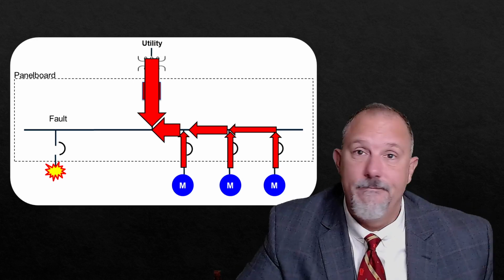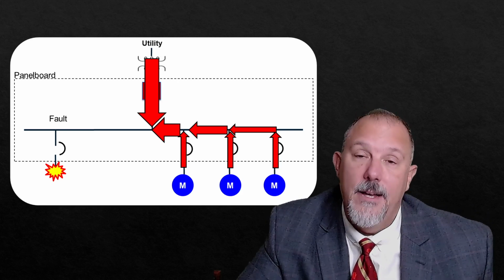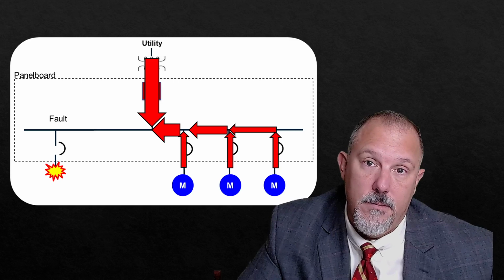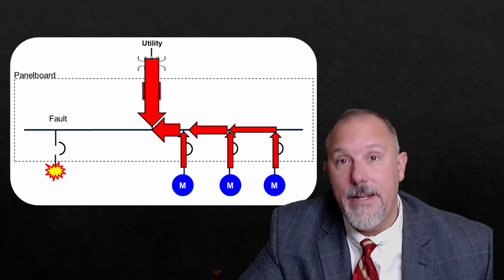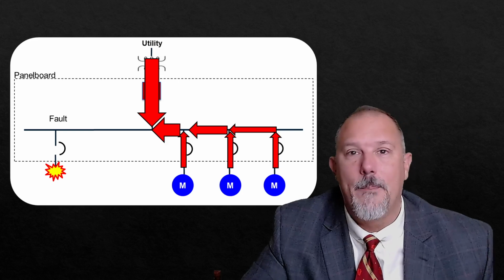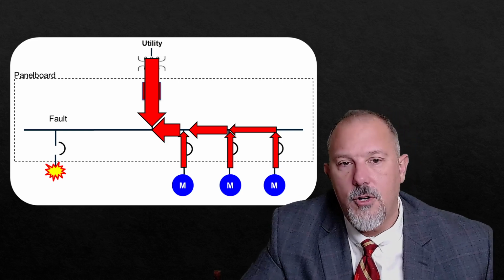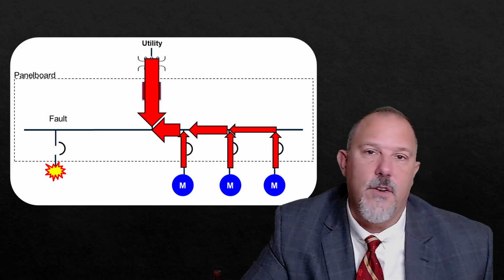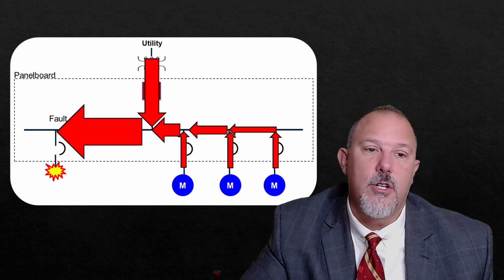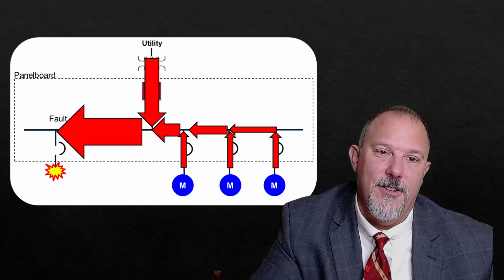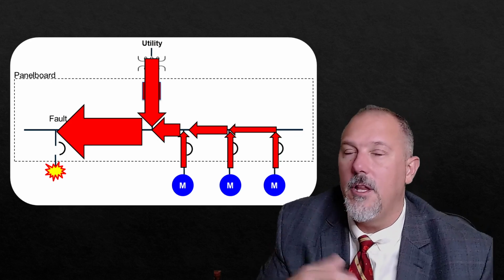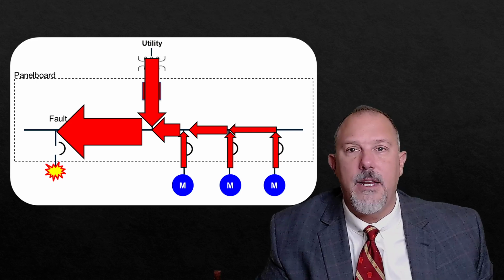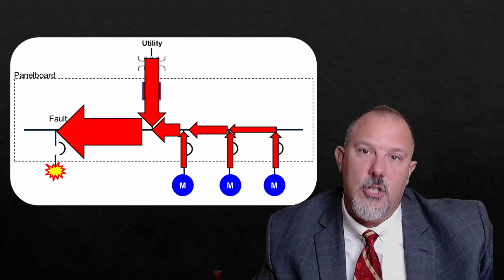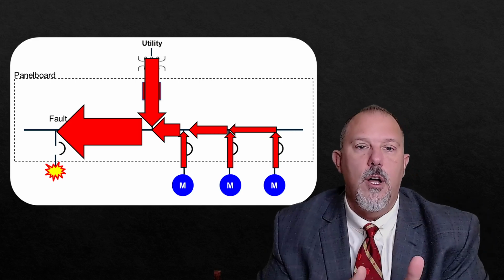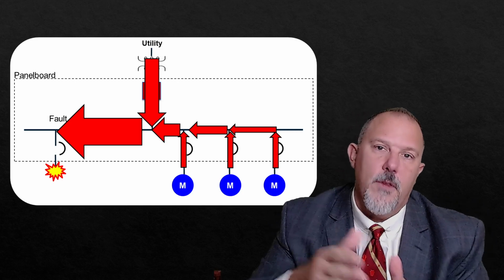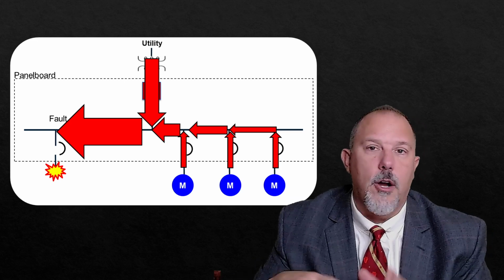And just like electrons are like party animals. They all want to go to the party. And they're lazy. They take the shortest path to the party. The party happens to be the fault. The motor contribution and the utility fault contribution will add to go to the fault current. So you really should understand, and for other reasons, if you do series rated solutions, you'll have to understand the flow of the motor contribution with regard to what overcurrent devices are interrupting what currents.